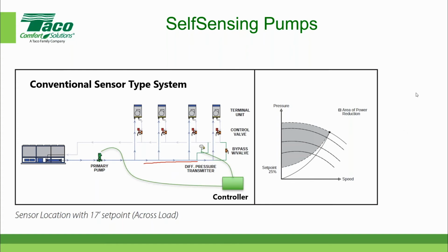So that's how a conventional system works. So what we're going to do next is we're going to say, okay, well, I understand how a conventional system works. And we're going to now talk about a self-sensing pump that does not use a pressure differential transmitter. It does not have a hardwired control signal to the controller. There is no controller external to the variable frequency drive, and there is no hardwired signal that goes to the variable frequency drive.